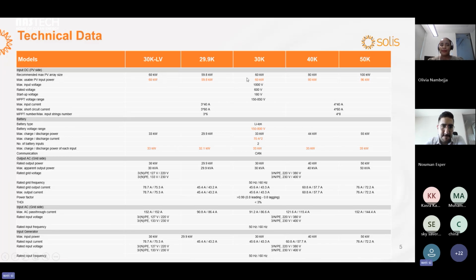For Solis inverters, you have 30 kilowatts of power to charge the battery, and you can use the 30 kilowatts of power to supply the load. For the battery, we support battery voltages from 150 to 800 volts, and we only support lithium batteries. This inverter supports 2 battery connection ports, so you can also choose to parallel the 2 DC ports together. Then we can realize a charging and discharging current of up to 150 amperes in total.